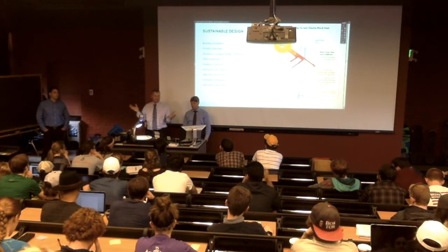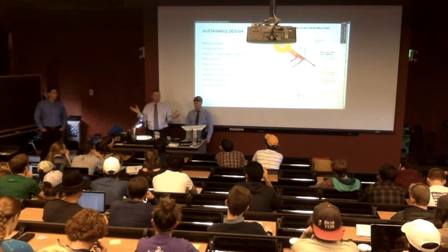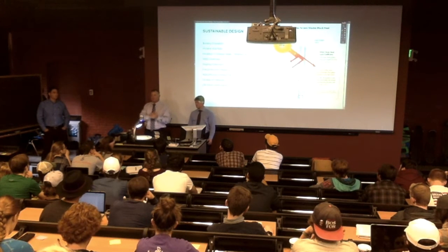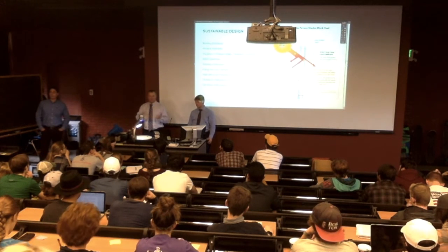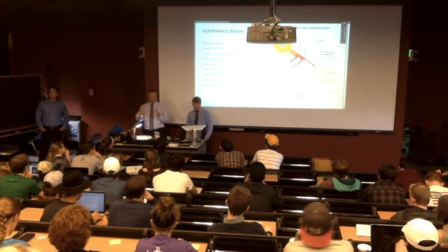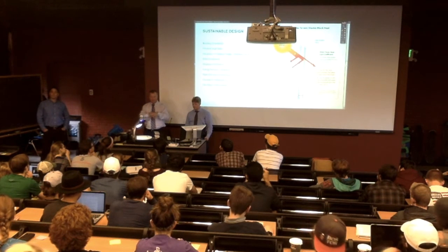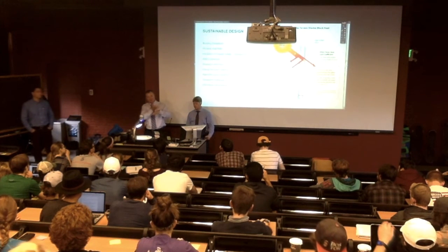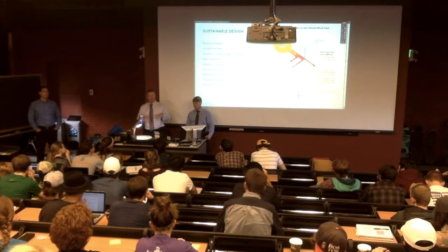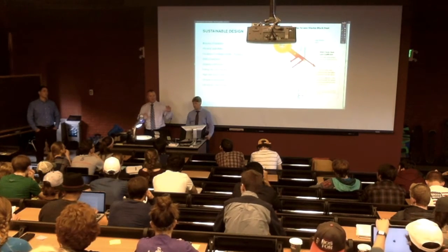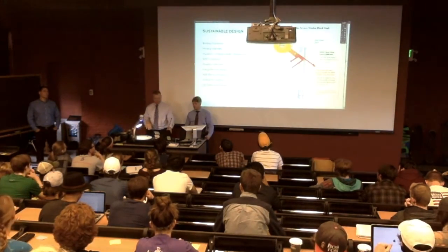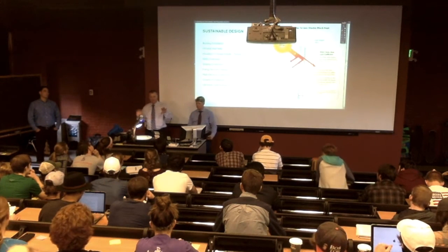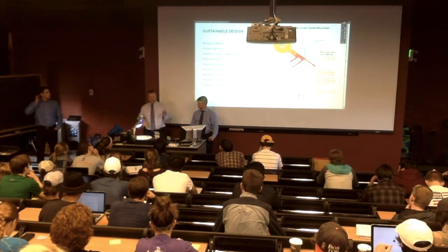So what do we do to make sure that the building is more efficient? We recover the energy that's being exhausted. There are a couple different ways of doing that. A heat wheel is one way, so the air passes through the wheel on one side, it rotates to the other side and preheats the air coming in. Another way to do it is a glycol system, a water-based system where the energy is transferred by a pump system.